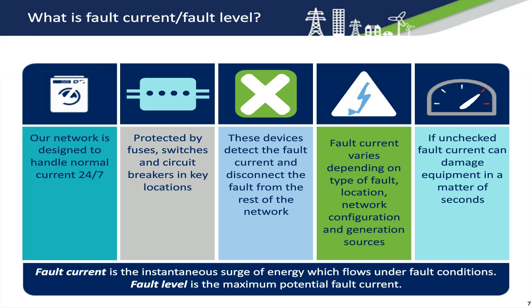The amount of fault current that flows will vary depending on the type of fault, its location, and how the network is configured and the sources of generation present on that network. If unchecked, the fault current can damage equipment in a matter of seconds. The fault level is the maximum we expect this current to be, i.e. the maximum potential fault current.